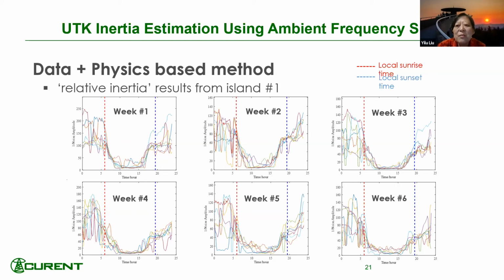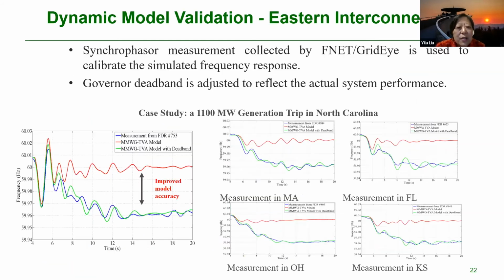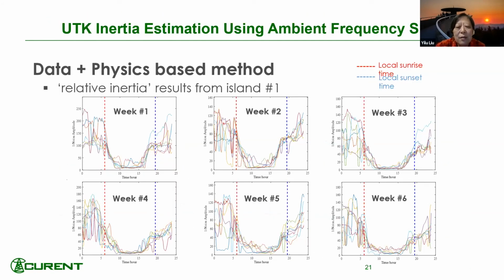Not to this extreme, but in a larger part of the US—this is a smaller island in Hawaii—the inertia varies quite drastically. So if you want to be careful, you need to know where your inertia is and how to compensate for that. This gives you good situational awareness for your system.